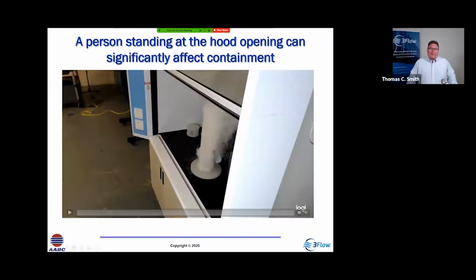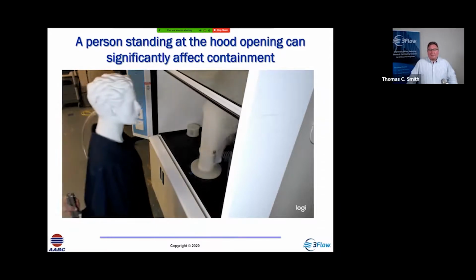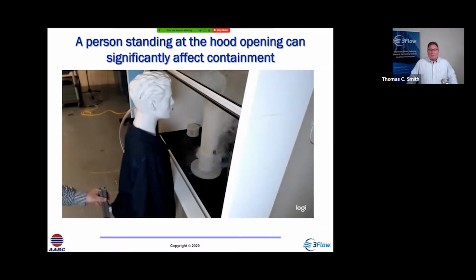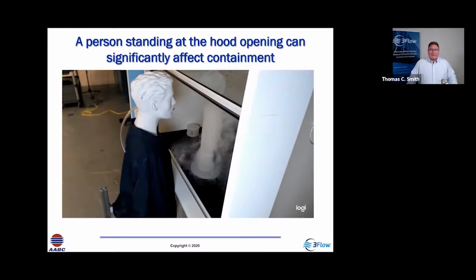Now, another thing is about the person standing in front of the hood. When a person walks in front of the hood, they affect the airflow patterns. And so when we're looking at this, we're generating our smoke with our fog generator, and we see that it's containing very well, but all of a sudden, here comes our mannequin or our person up to the hood. And when we see that occur, we see a dramatically different set of airflow patterns.